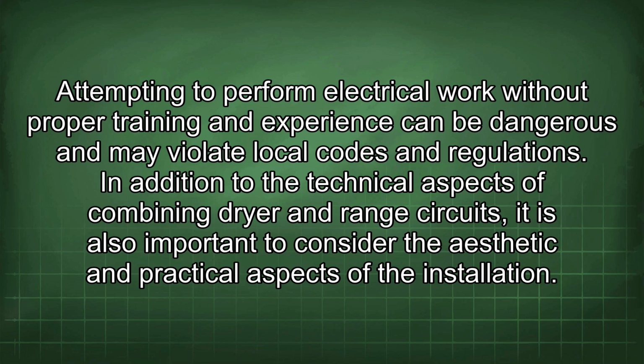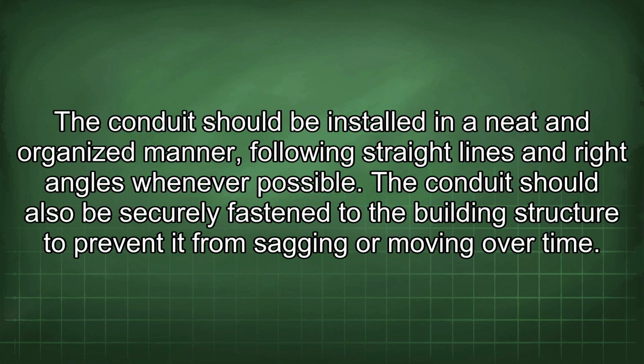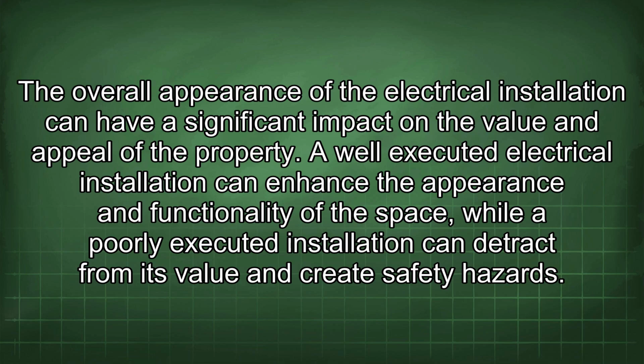In addition to the technical aspects of combining dryer and range circuits, it is also important to consider the aesthetic and practical aspects of the installation. The conduit should be installed in a neat and organized manner, following straight lines and right angles whenever possible. The conduit should also be securely fastened to the building structure to prevent it from sagging or moving over time. The overall appearance of the electrical installation can have a significant impact on the value and appeal of the property.